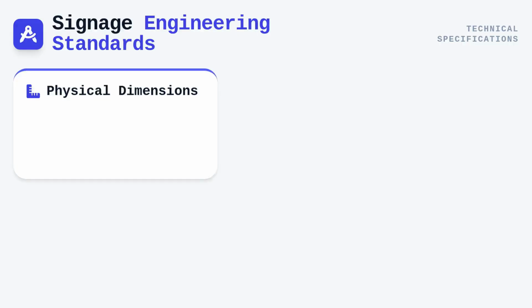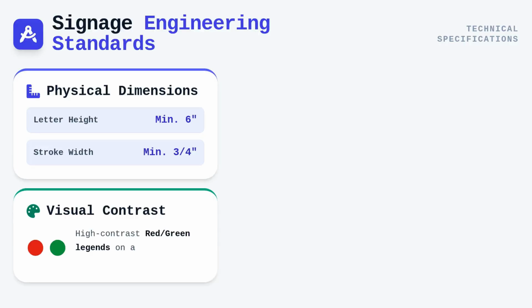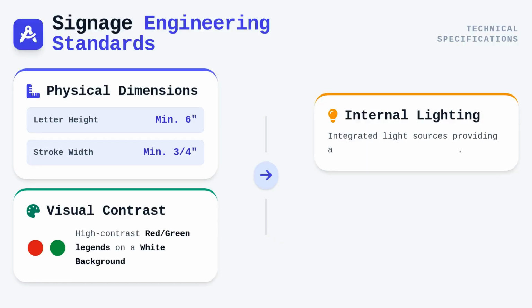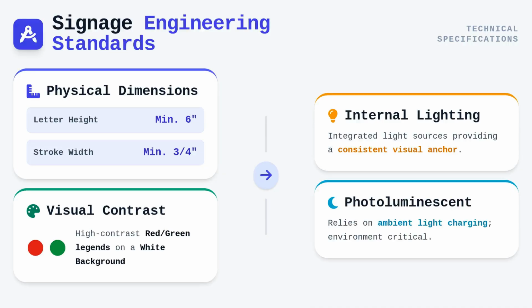The physical characteristics of these signs are governed by strict engineering standards to ensure they function when it matters most. Lettering size, width, and contrast are not arbitrary choices, but calculated dimensions meant to maximize recognition. Typically, we require the letters to be at least 6 inches high, with a stroke width of at least 3/4 of an inch. Contrast is equally important. A red or green legend on a contrasting background, usually white, must be maintained to ensure the characters remain discernible even at a distance. When we talk about illumination, we generally categorize signs as internally or externally illuminated, or sometimes photoluminescent. Internally illuminated signs are often preferred because they contain their own light source, providing a consistent visual anchor. Photoluminescent signs, while useful, rely on a charging period from ambient light, which necessitates careful consideration of the lighting environment they occupy.